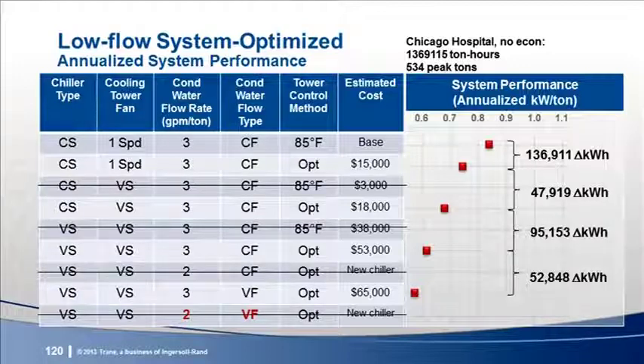Chiller tower optimization is a wild card. How capable are the existing chiller plant controls? Now, I've assumed that all alternatives are going to need a controls upgrade anyway. So, which other options can we eliminate? It sure looks like optimum tower temperature control, even on single-speed towers, is a no-brainer that allows us to unlock the other options. We're now down to 3 further levels of performance: variable speed tower fans, variable speed chillers and towers, or going all variable speed, including the condenser pumps.